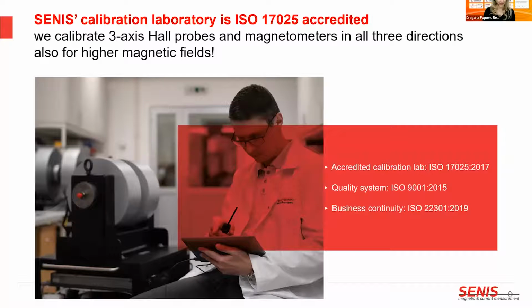We know how to calibrate 3-axis sensors and magnetometers. As shown on the previous slide, we have a patented solution which enables us to determine very precisely the orthogonality of the 3D Hall sensor, and the Senis calibration laboratory is ISO 17025 accredited. We calibrate in all 3 directions, also for higher magnetic fields.